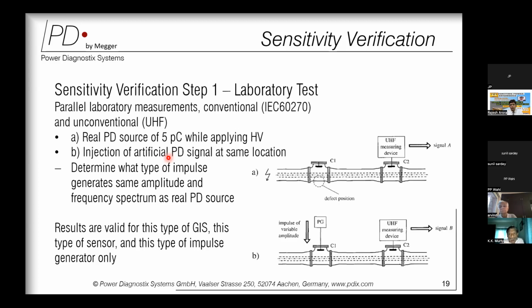The first is verification step 1, which is performed in a laboratory. Here, parallel measurements are performed in a laboratory. One is as per the conventional IEC 60270, which is a horizontal standard explaining the measurement procedure of partial discharge. The second is an unconventional UHF measurement. These two are performed in parallel on a portion of a GIS.